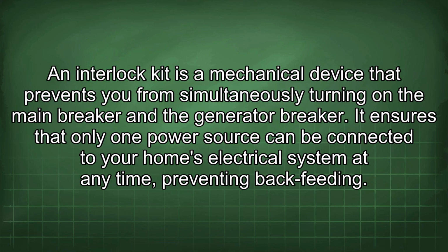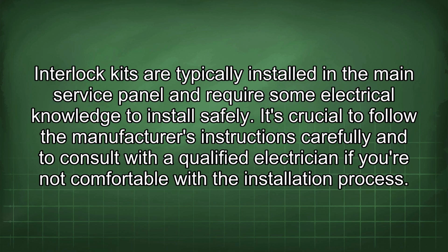An interlock kit is a mechanical device that prevents you from simultaneously turning on the main breaker and the generator breaker. It ensures that only one power source can be connected to your home's electrical system at any time, preventing backfeeding. Interlock kits are typically installed in the main service panel and require some electrical knowledge to install safely.